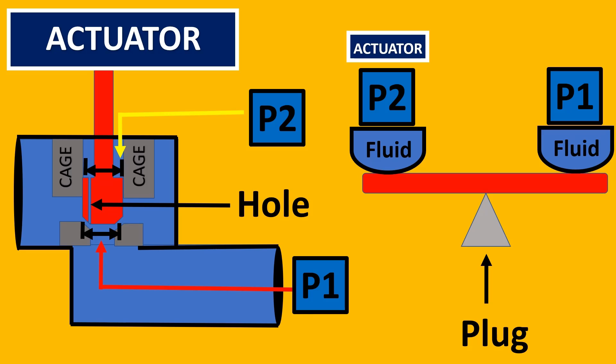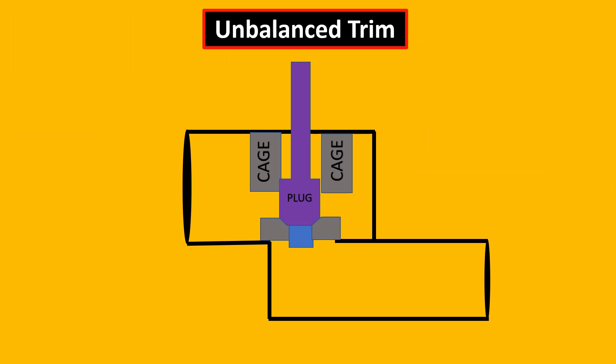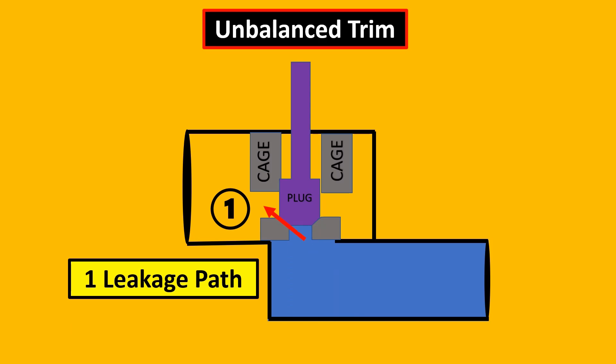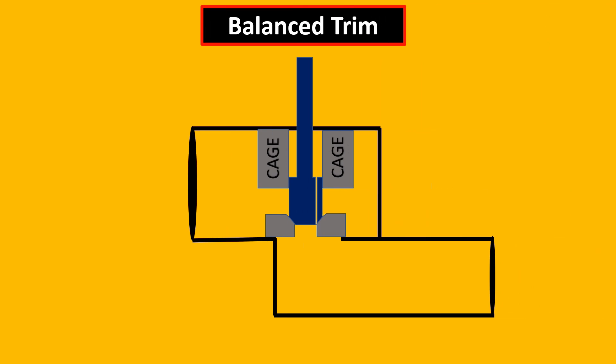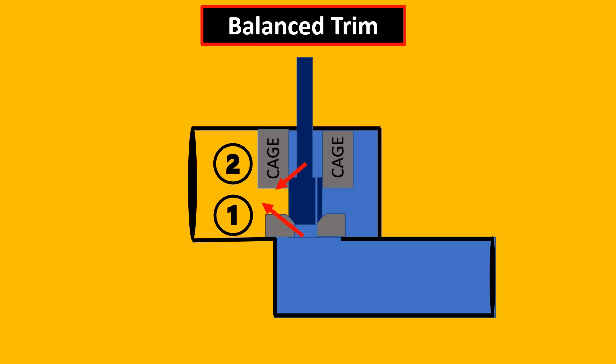Now if you notice, you might think we should always go for a balanced design, right? But that is not the case. In an unbalanced trim, there is only one leakage path. But compare that to a balanced design—because there is flow through the hole, there are two leakage paths possible. This is one of the biggest drawbacks of a balanced trim design.